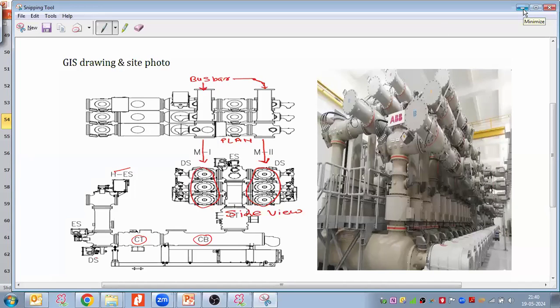Why am I telling this point? Because as a design engineer, you might be aware of the equipment, but when you are sending this drawing to the site for construction, and if you are taking the modular type GIS, we have a separate module for each equipment. In that case, the modules have to be bolted or connected at the site with the help of a crane. So if you have given a clear equipment module, it will be easy for the site engineer for the assembly of the module, right? Due to that reason, I'm telling this point.